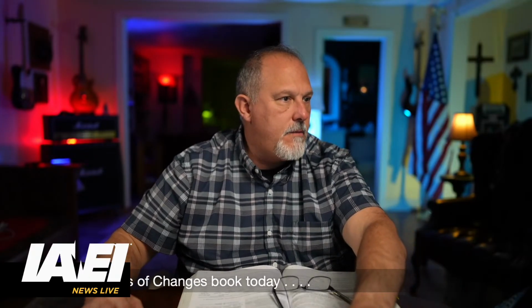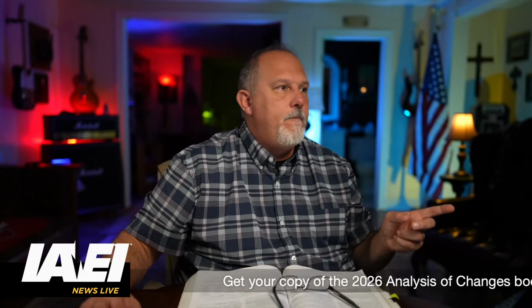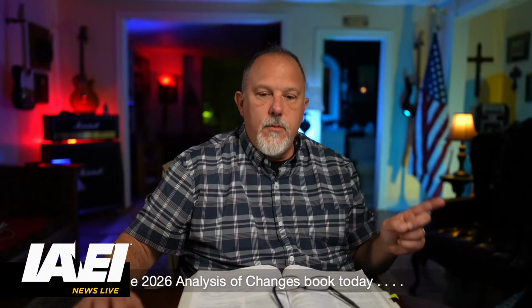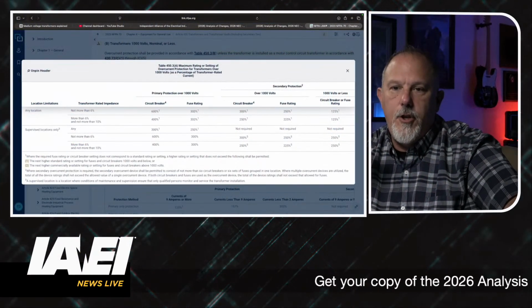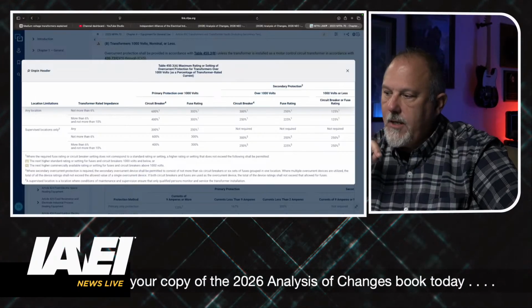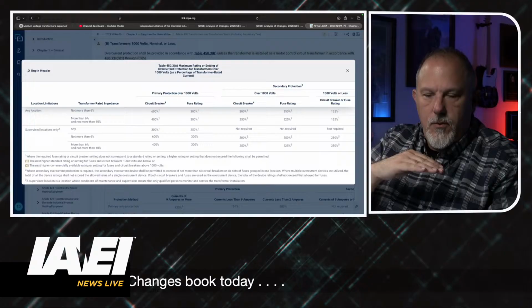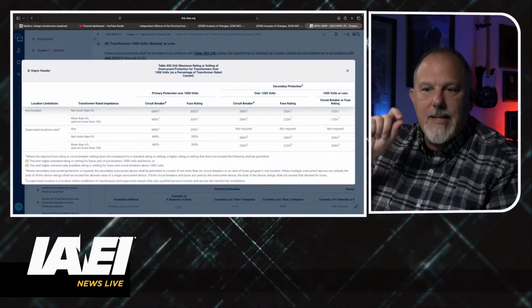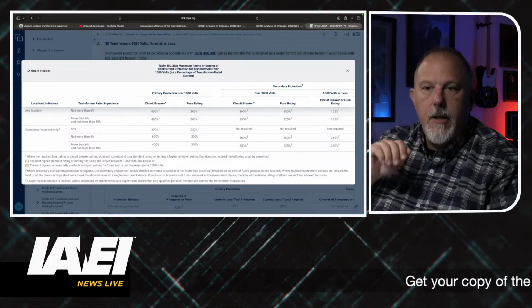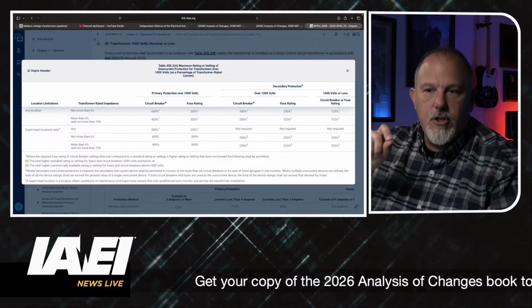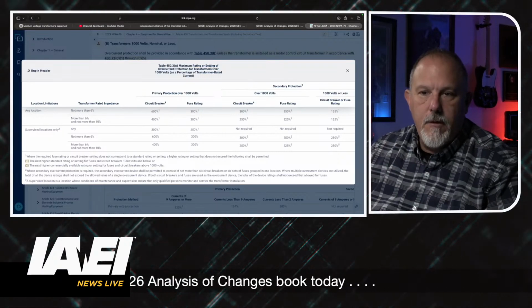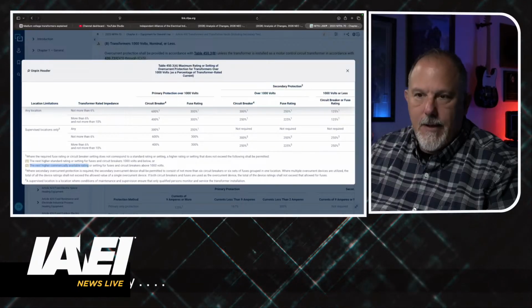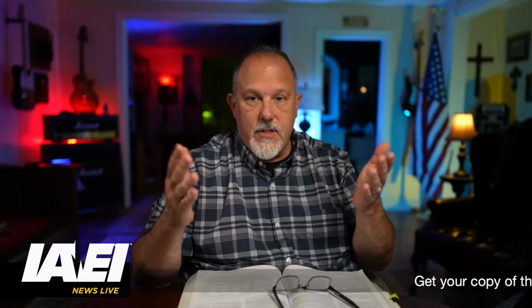Can I zoom in on this? Can I? I can't. Whoa. No, I can't. So think about this. It says in note 1, take a look at down below where you have 1 and 2. 1 says the next higher standard rating or setting, and 2 says the next higher commercially available rating. Check that language out right there. I know it's kind of hard to see, but I'll just speak to it.